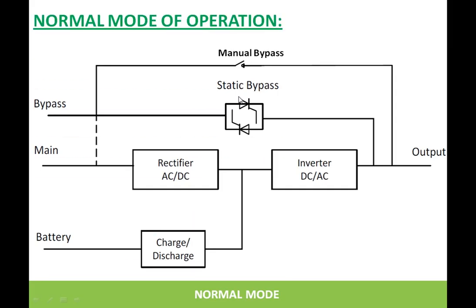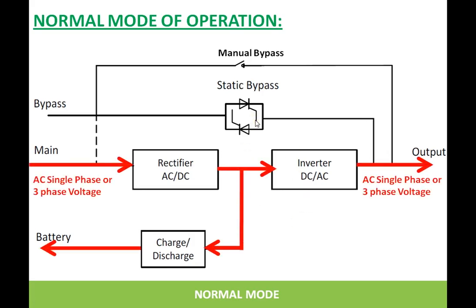This is the normal mode. Whenever the UPS is in a healthy condition, this is the mode that the UPS is in. The red color arrow shows the power flow: mains through the rectifier, then the inverter, and to the output. At the same time, the rectifier output is used for charging the battery.